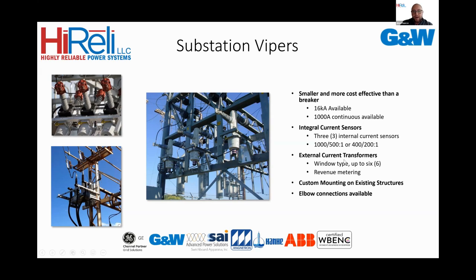We can also get 5 amp secondaries if you have different relays that need different inputs there. We can mount onto existing structures, which is the main picture in the center. So if we know what you want us to mount the Viper modules on, we can create custom mounting to mount to your structures. And then the Viper insulators are removable, the gray insulators on there, and underneath the insulator is an elbow connection, ANSI elbow connection. So you can see the riser pull on the bottom left. We can give you elbow connections on the horizontal, the vertical bushing, or both. So if you want to get some extra animal protection at substations, you can use elbows instead of live terminals.